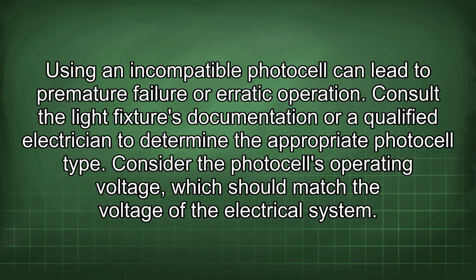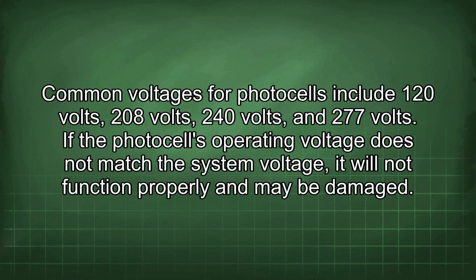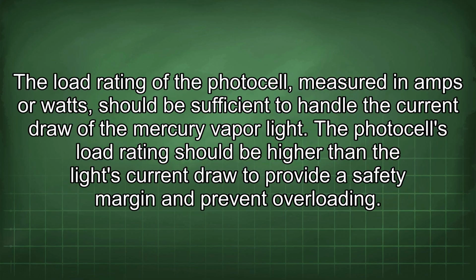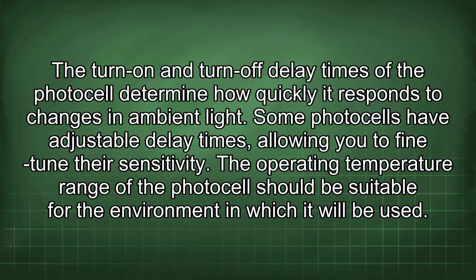Consider the photocell's operating voltage, which should match the voltage of the electrical system. Common voltages for photocells include 120 volts, 208 volts, 240 volts, and 277 volts. If the photocell's operating voltage does not match the system voltage, it will not function properly and may be damaged. The load rating of the photocell, measured in amps or watts, should be sufficient to handle the current draw of the mercury vapor light. The photocell's load rating should be higher than the light's current draw to provide a safety margin and prevent overloading. The turn on and turn off delay times of the photocell determine how quickly it responds to changes in ambient light.